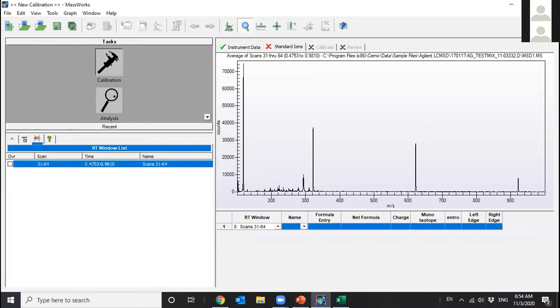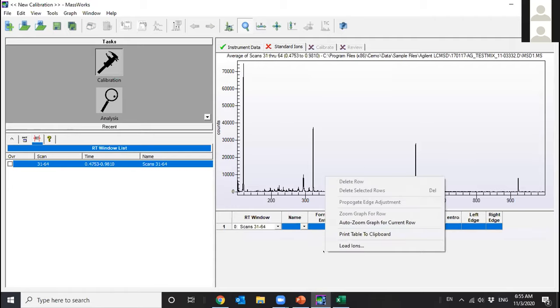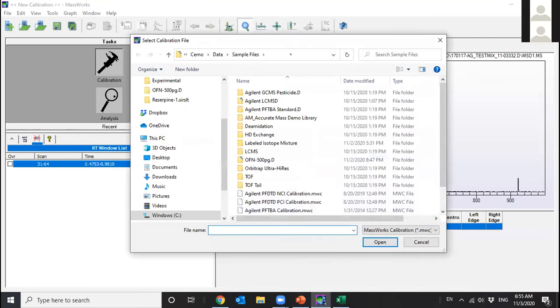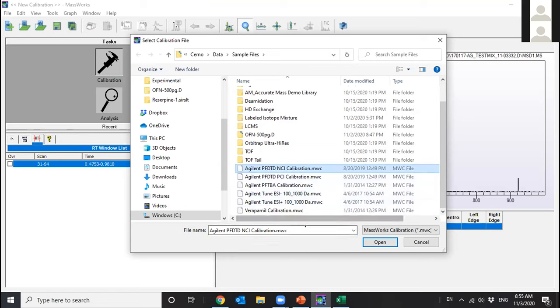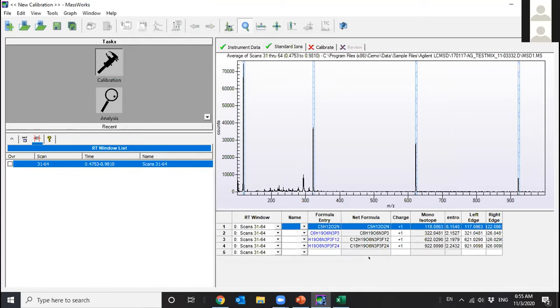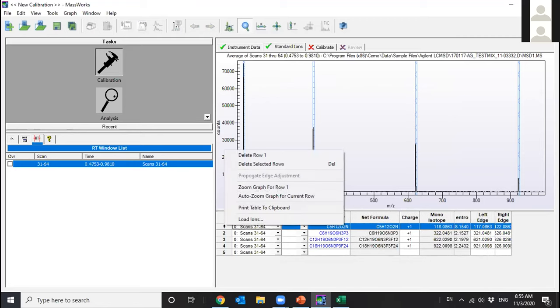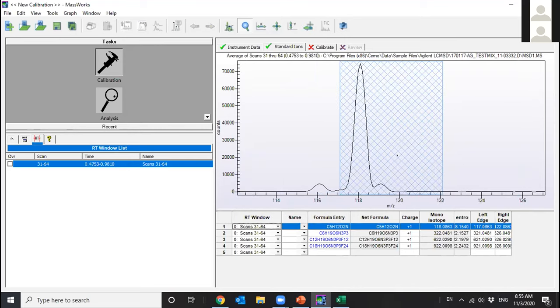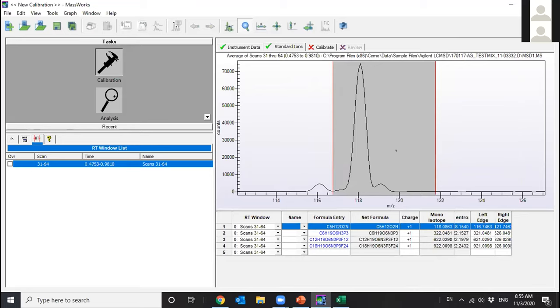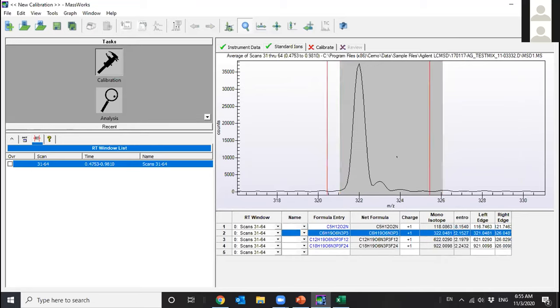And then you go to the standard ions tab here. This is where you enter the elemental composition of the standard ions for the Agilent tune solution. Fortunately, today we already built in this table for you. All you need to do is move the mouse over at the bottom of the screen and select load ions. That should take you to the default installation data directory, where there are Agilent pre-built calibration files. And we are looking for electrospray plus ion between 100 and 1000. So you open that, and that will automatically fill in the elemental composition for the various standards that you want to use for the calibration. You might need to adjust the shaded window for the various standards so that the window starts from baseline and ends at the baseline.